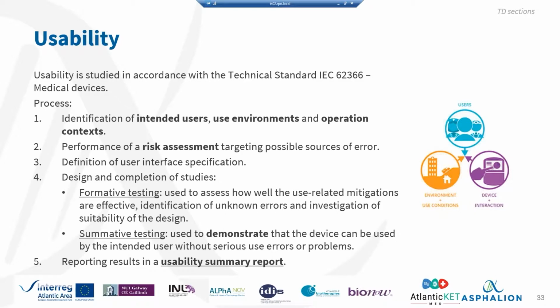And then you've got to design studies. There are two types of studies for usability: formative testing and summative testing. So what is formative testing? Formative testing is something you do while you are developing your device.